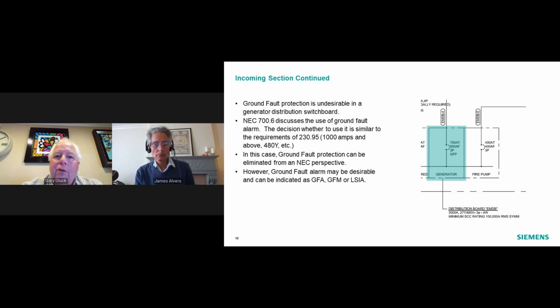700.6 discusses the use of ground fault alarm. That is something that is desirable in an emergency generator distribution switchboard. The criteria that people typically use is similar to the criteria that we see in 230.95, which obviously applies to service entrance boards, and this isn't a service entrance board, but we typically will see ground fault protection at 1,000 amps and above, and at 480Y. So, in this particular case, ground fault protection could be eliminated from an NEC perspective. And as I said, ground fault alarm may be desirable, and we see it shown on drawings in a variety of different forms: GFA for ground fault alarm, GFM ground fault monitoring, LSIA, long time, short time, instantaneous alarm.